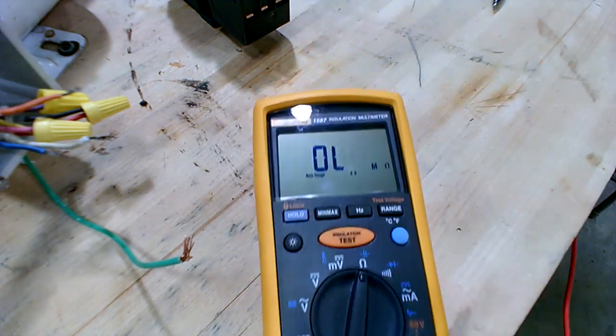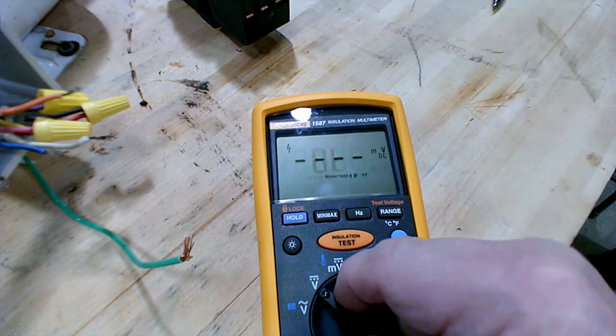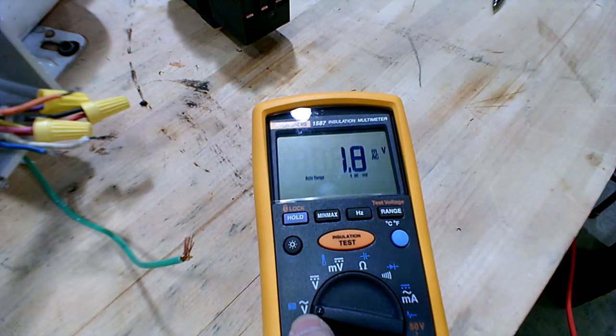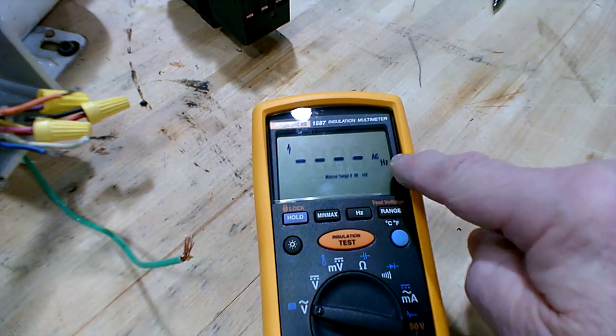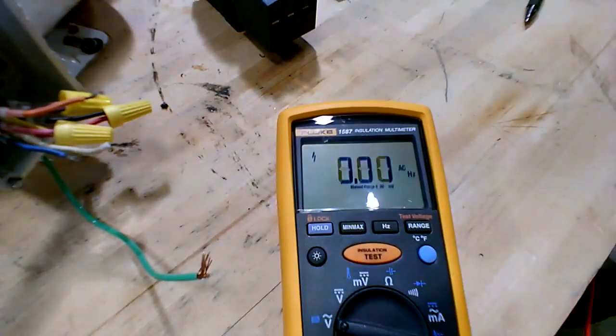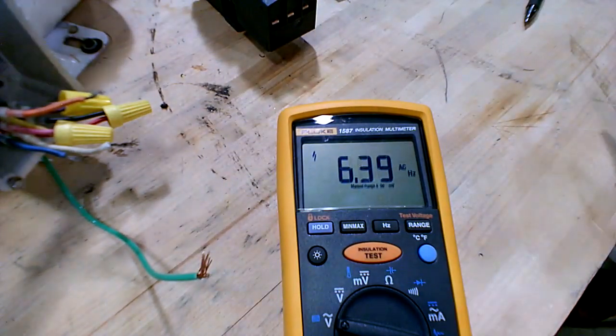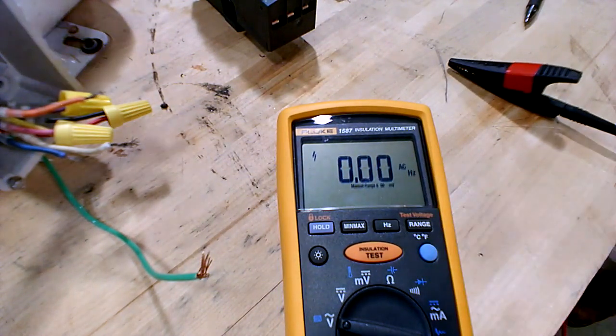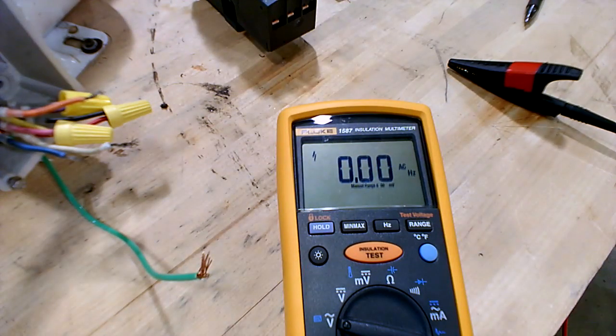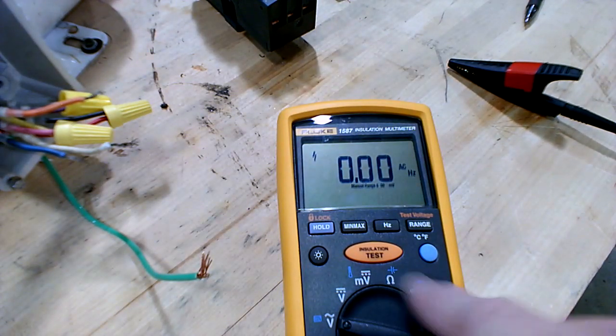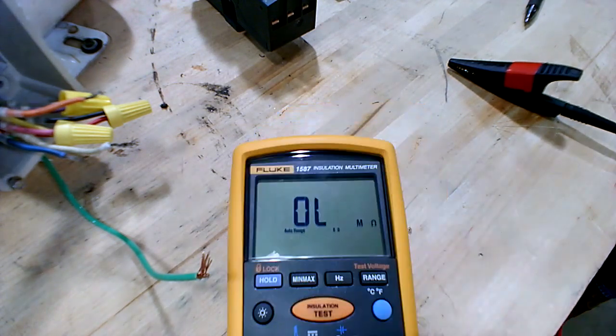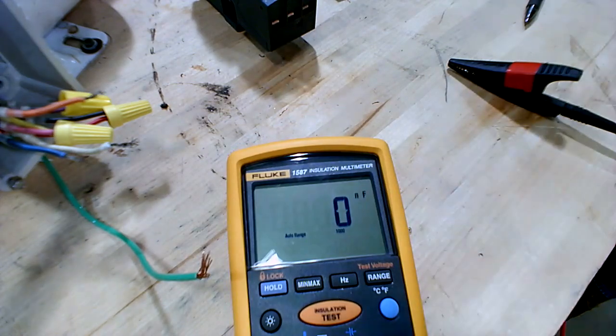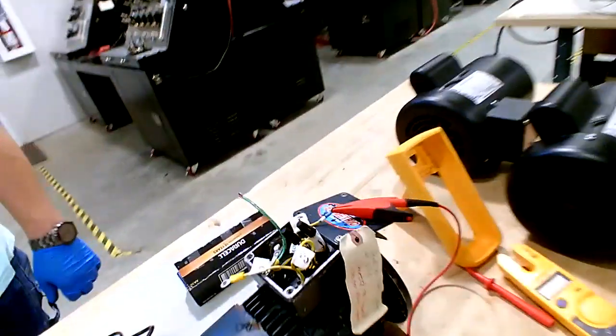It'll also do frequency. If you go to AC volts and hit hertz, it reads the frequency of whatever. If you're checking a drive, a VFD, it'll actually tell you hertz. To check capacitance, get in the blue function. If you go to ohms and hit the blue button, it goes over to farads. It'll check a capacitor, like on the back of the motor here.